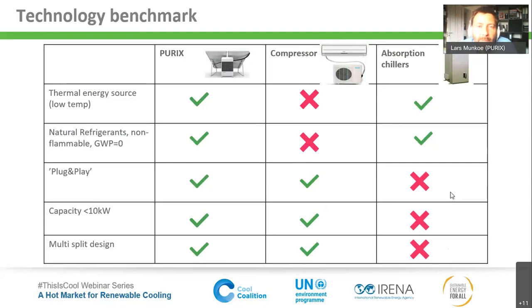So what we did was cherry-pick the solar thermal energy supply, and then redesigned an absorption chiller using water and lithium bromide, and put that together in a package similar to a multi-split air conditioning system. This gave us the advantages of a flexible and modular design that end users are familiar with, split, plug and play, addressing the low capacity market, which is essential for the rising cooling demand, using water with a global warming potential of 0, and low temperature heating instead of electricity.